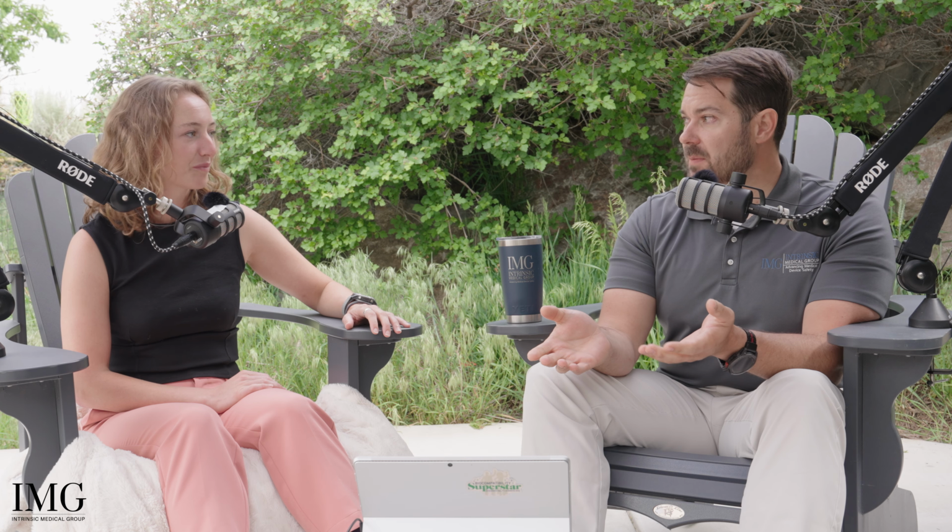So when you talk about implantation, one of the setups and designs is the length, right? How long are you going to do an implantation study for? That should reflect the clinical use of your device. When we're talking about a permanent implant, you're not going to go years in an implantation study. Generally, for the United States and CE regulatory markets, you look at around 13 weeks to replicate long-term. And from my understanding, that's scaled from a human lifespan down to the animal model lifespan, right? Correct. That was the initial premise behind it.